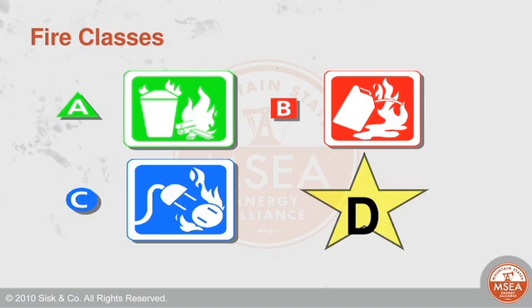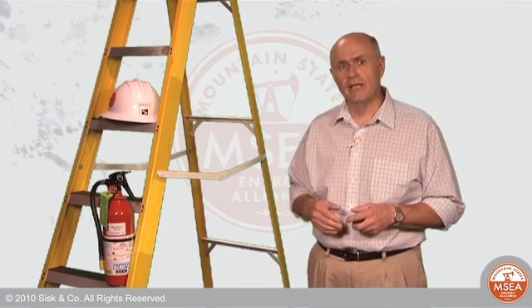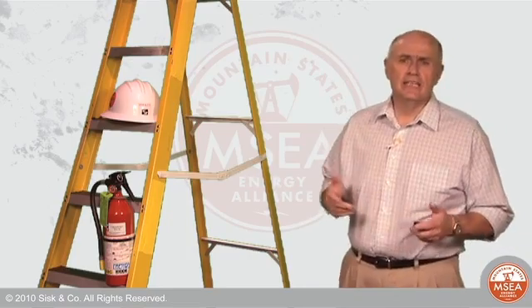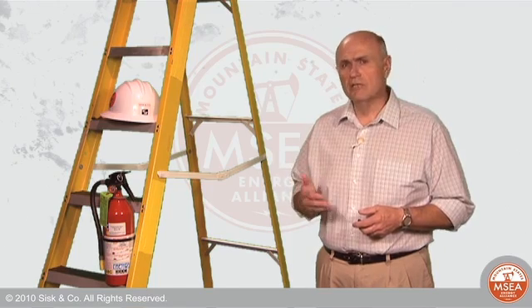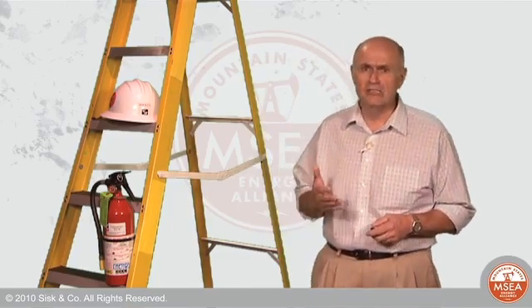Electrical, or the C-type fires, really means that they're electrically energized. It's going to be a type A material or a type B material that is most likely burning, but the ignition source is going to be from an electric arc. And a Class D fire is really a flammable metal. These might be things like aluminum, magnesium. These are going to be exposures in probably machine shops or other type of operations where you're using some of those type of metals.